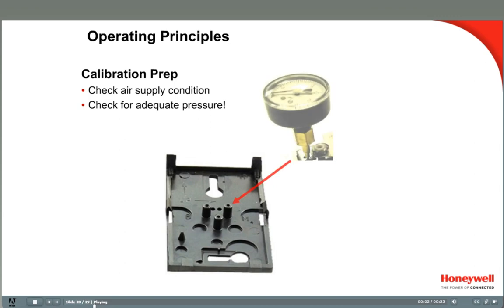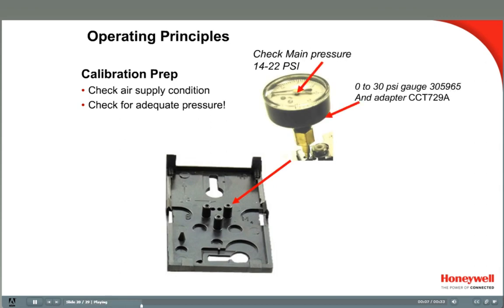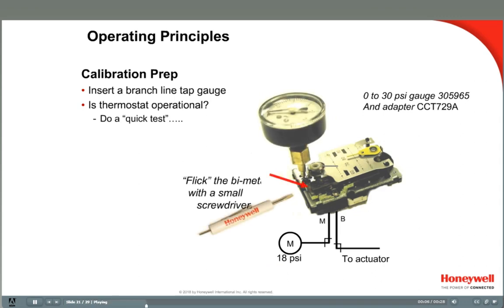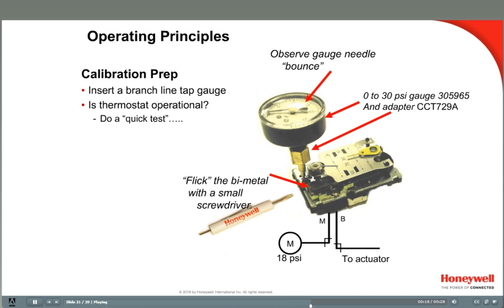Before you calibrate, make sure you're getting enough air to the stat. The recommended main air pressure is usually 17 to 22 pounds and almost always needs to be at least 14 pounds. Check main air pressure by removing the stat from the wall and inserting a branch tap gauge into the main air port on the exposed back plate — it's marked with an M. If the main air pressure is low, check for air leaks, crimped tubing, dirty filters, or an incorrectly set pressure-reducing valve. Also make sure the stat is operational — give the bimetal a couple of quick flicks to see if the branch line tap gauge needle bounces.